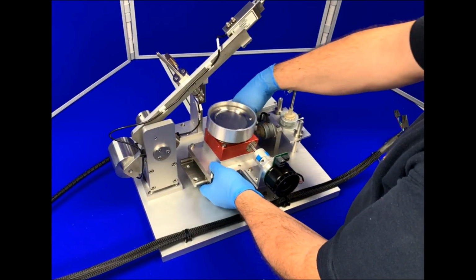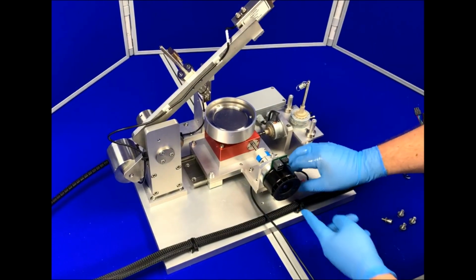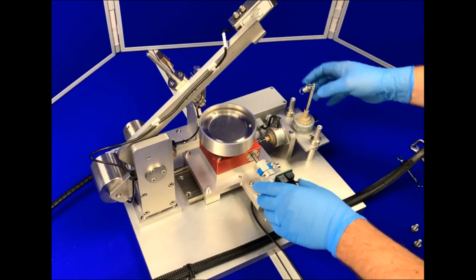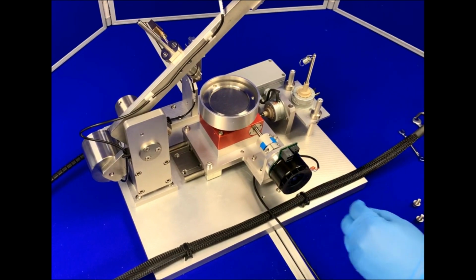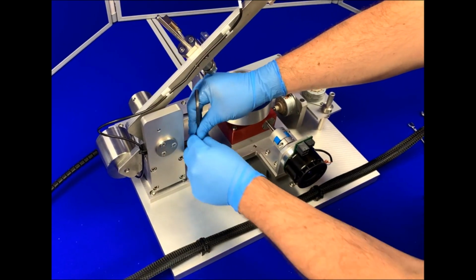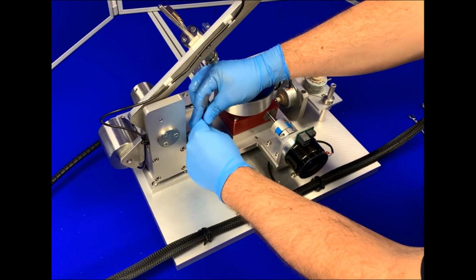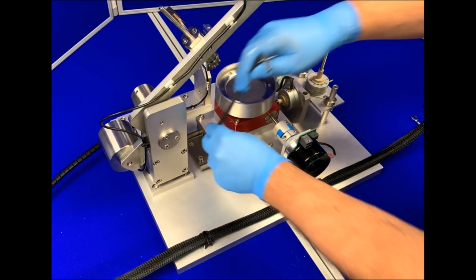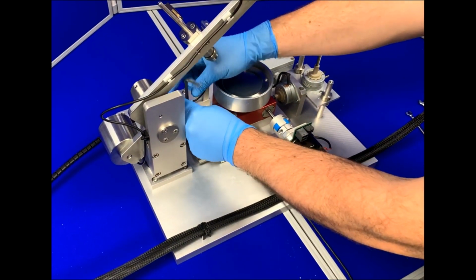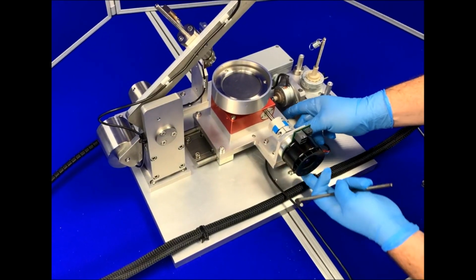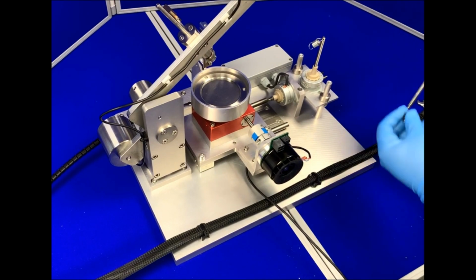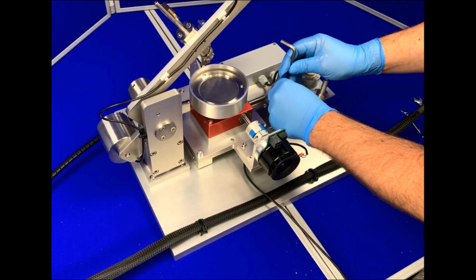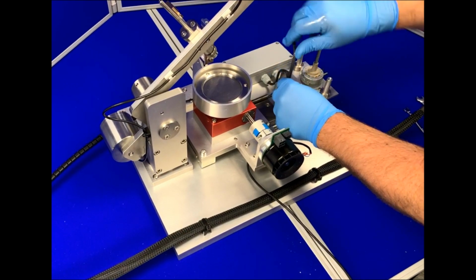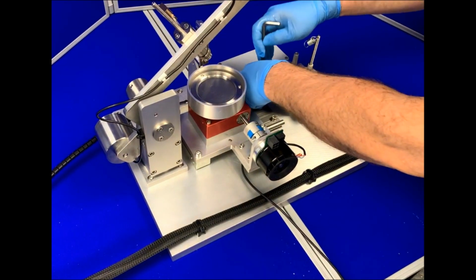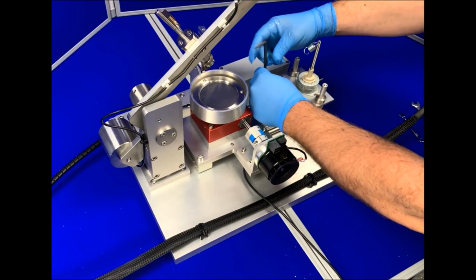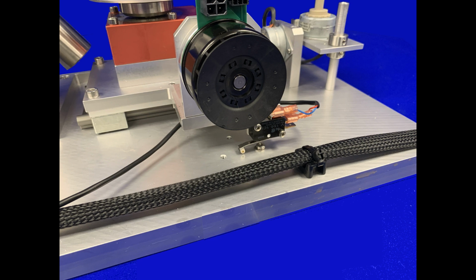To install the pin on disc module, place the module on the locating pins on the base plate. Secure the slide with the 4 cap head screws provided. You need to slide the carriage from one end of its travel to the other in order to expose 2 of the screws. But while doing this, make sure that you lift the home switch roller lever so it does not get bent on the detection screw.